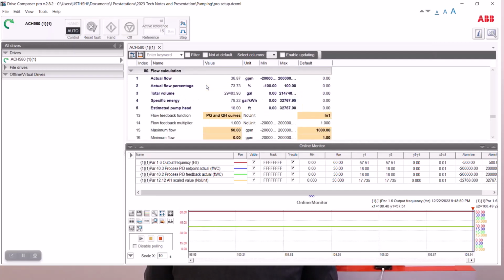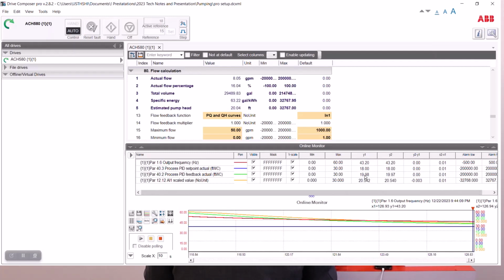Let's take a look at what happens when I change the system. I'm going to change my throttling valve and drop my flow down. Okay? So I've dropped my flow down. The whole entire system's starting to change. What you're seeing is now the speed of the drive is slowing down. My pressure ended up being a bit high. It's trying to catch up to my set pressure right now, but my actual pressure on the output and my scaled pressure are relatively very close to each other right now as the drive slows down to a point where these numbers start to line up.